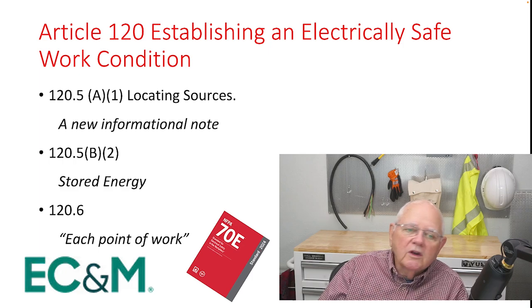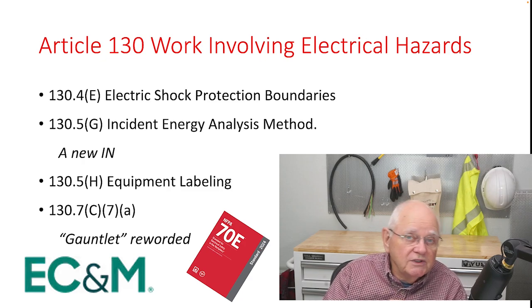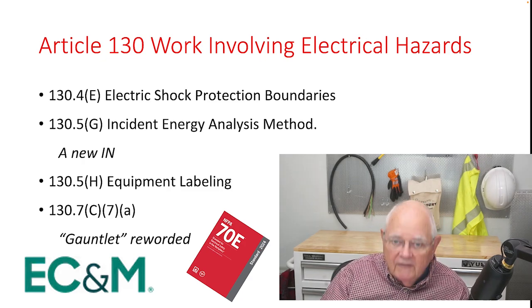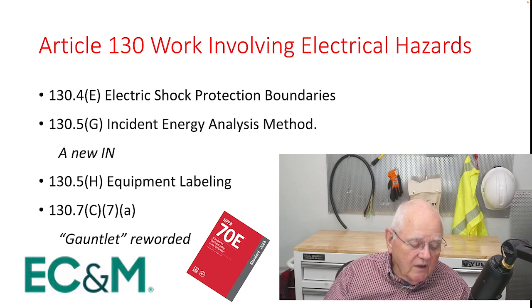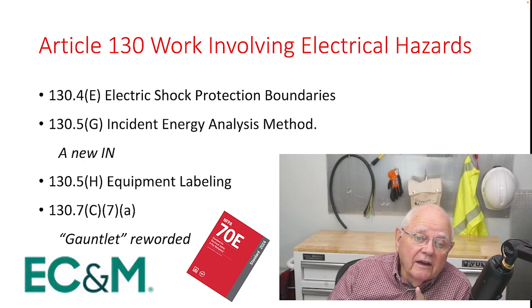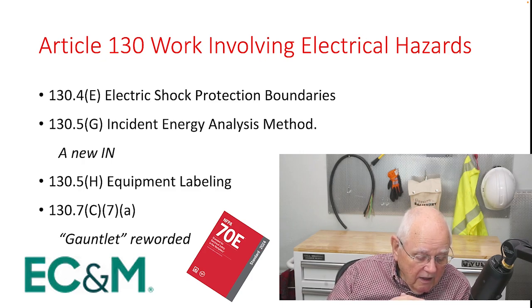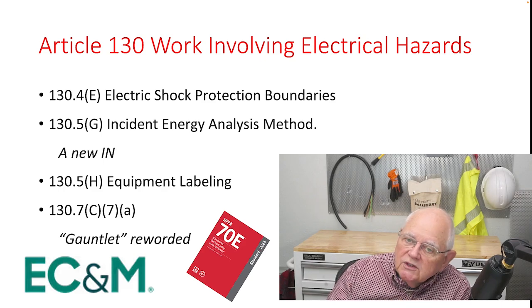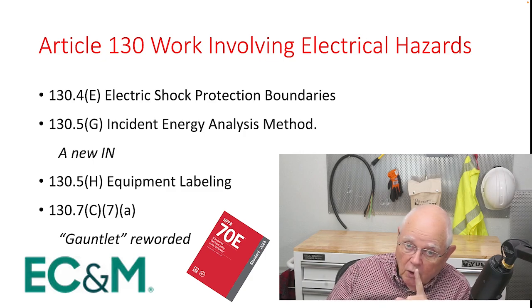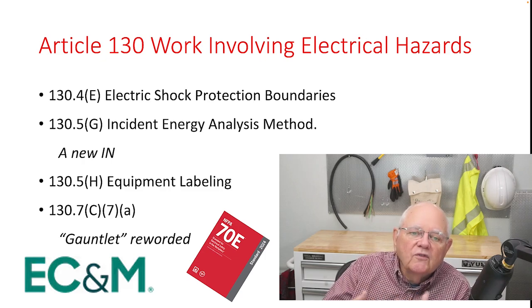Article 130 is work involving electrical hazards. There's been a change to the shock protection boundaries table, 130.4(E). That's on page 26, once again, if you're following along. And it looks like very minor changes. They have added a new line in there on the AC shock protection boundaries, and they've broken up the medium voltage levels. So now we have 751 V to 5 kV and 5.1 kV to 15 kV. And what's changed is the restricted approach boundary distances have changed by 1 inch. Certainly nothing major there, but it's to conform with the requirements for rounding our numbers off.